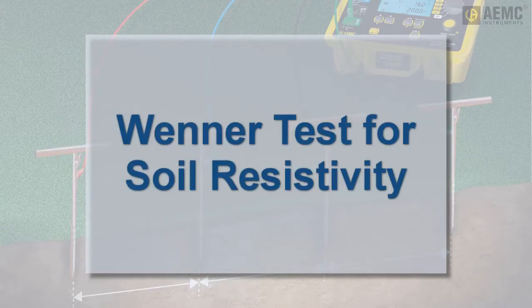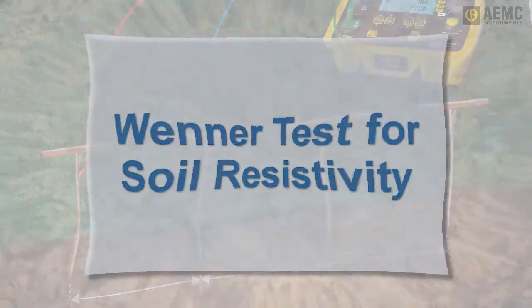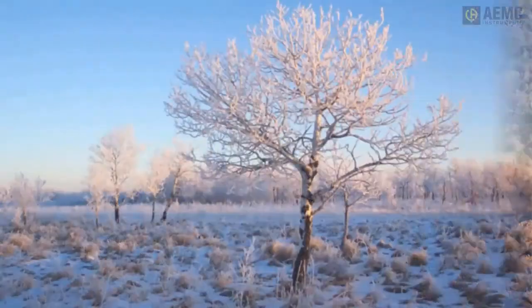Soil resistivity is a key factor for determining what the resistance of a grounding electrode will be, to what depth it must be driven in order to obtain low earth resistance, and even the type of grounding system that should be designed for this location and facility. The resistivity of the soil varies throughout the world and changes seasonally.